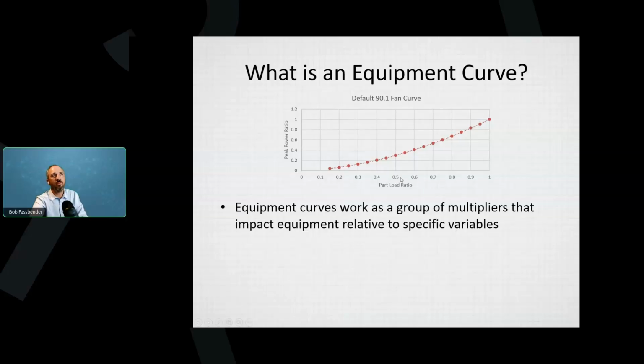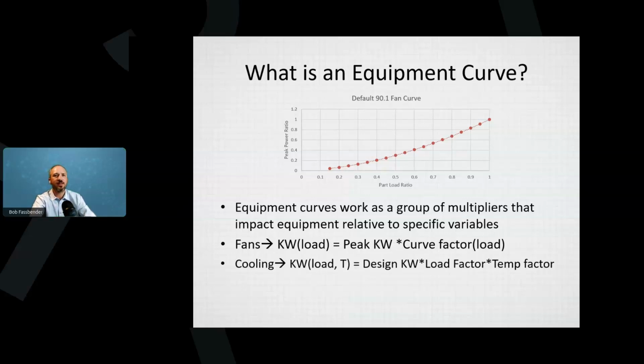But if we looked at 0.5 and followed the curve, we're looking at 0.3. So if you cut off half the load, you'd be at about 30% of the power. That's actually a pretty conservative curve, because fans typically unload a lot better than that, which we'll get to. This is just the mathematical function: a function of the load gives the multiplier, times the peak kilowatts. For cooling equipment, it's a lot more complicated than that. There's a bunch of multipliers. I won't get into that detail. I'll just show you an example.